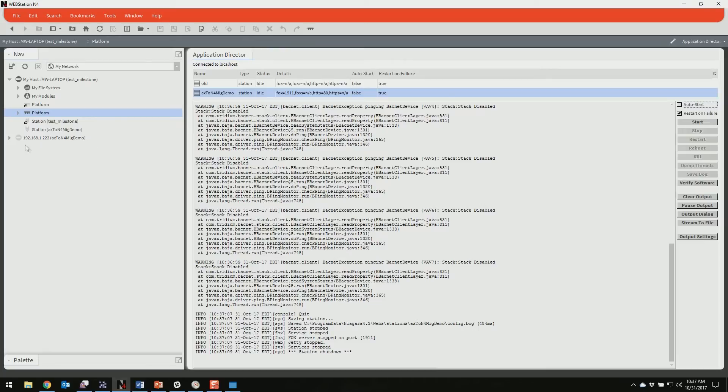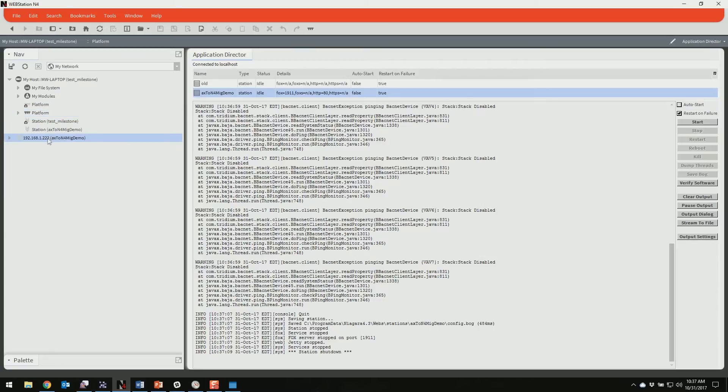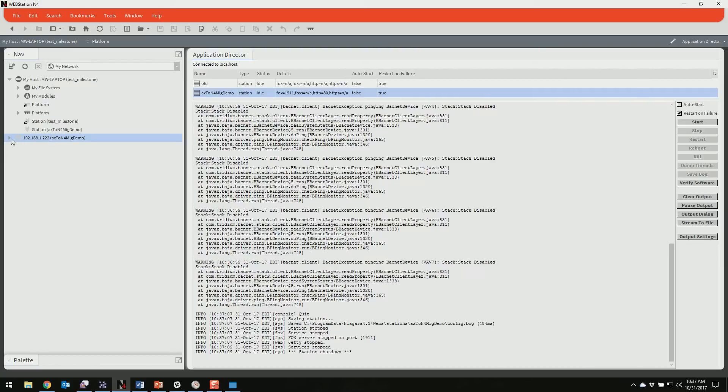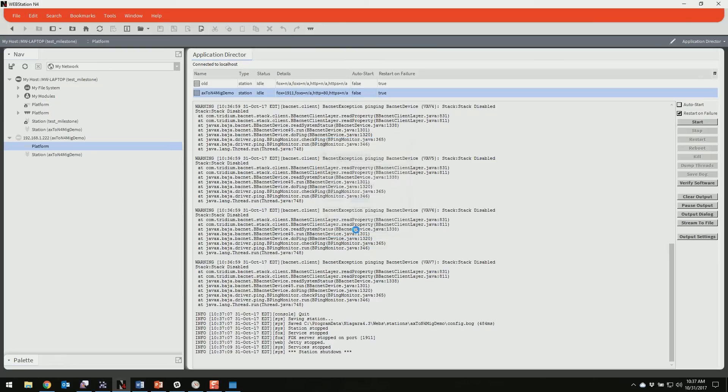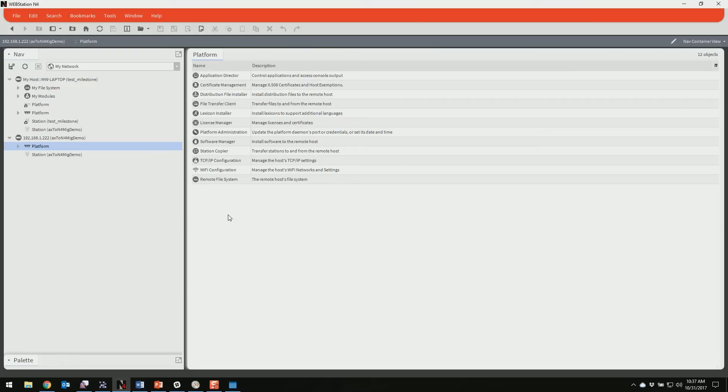And the next step, last step actually, is going to be to commission the Jace. Now, when you pull a Jace out of a box, it's going to be at 192.168.1.140 as its default IP address. For Johnson, it's 192.168.1.149. So I'm running a Jace on our network here. It has a different IP address, but everything else is exactly the same. So just keep in mind this 222 for you may be 140 or 149. So I'm going to log into the platform here.